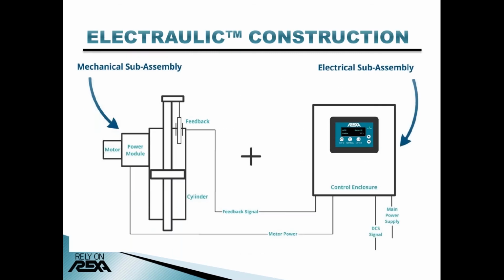The Electraulic technology consists of two primary components, the mechanical subassembly and the electrical subassembly. The mechanical portion is attached to the driven device, which in this case would be a butterfly valve. The electrical assembly is basically the positioner for the actuator. This is where the main power supply and control signal are routed and the origination of 4 to 20 milliamp position feedback for connection to the DCS or other control system. We separate the electric and mechanical assemblies for ease of access and operation. There are many severe applications, for example, in mining and desert environments, where onboard electronics simply would not survive. The control box can be mounted in a convenient location to the valve or up to 700 feet away.